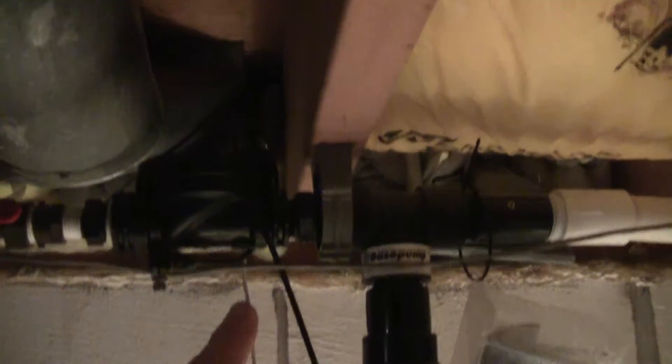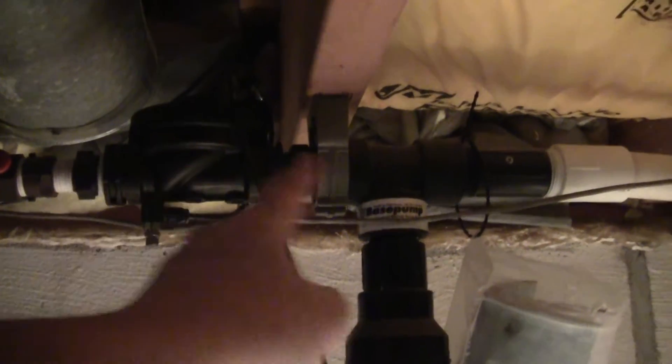It opens the valve, and then the city water pressure goes through this little chamber here and creates a vacuum. So for every one gallon of city water that flows through, it sucks out two gallons of water out of the sump. When you lose power, chances are you don't lose city water pressure.